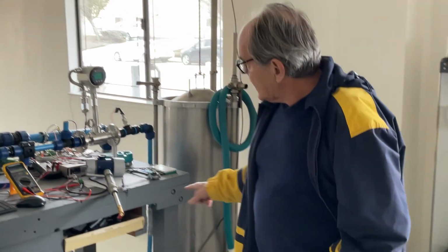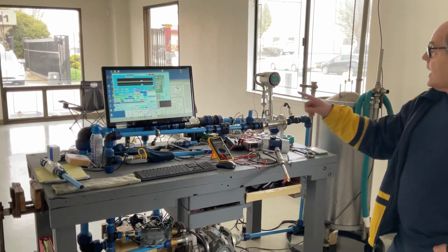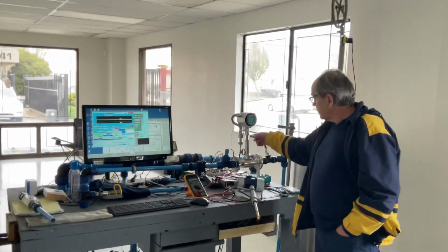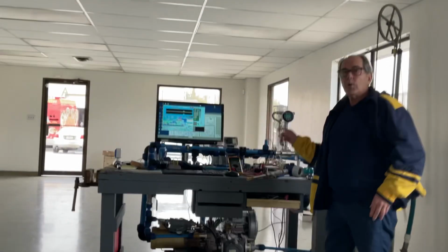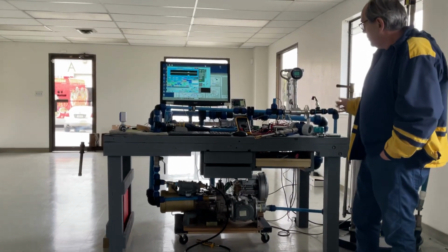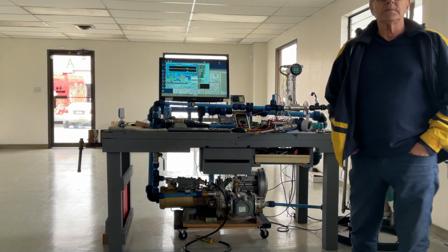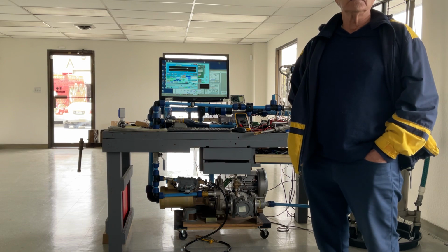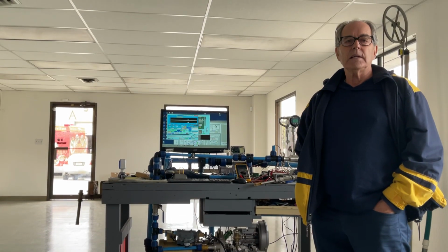But nonetheless, once it's closed and there's no leaks, it's flowing gas, that gas that you put into it, we now characterize this flow meter, or whatever flow meter, with that gas, with this closed loop system. So I just want to back up here, and this lets us know exactly how much flow is flowing through the system, and then we can use that to calibrate. That's right. Is that accurate?